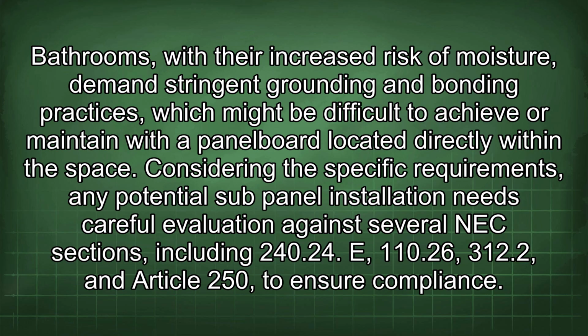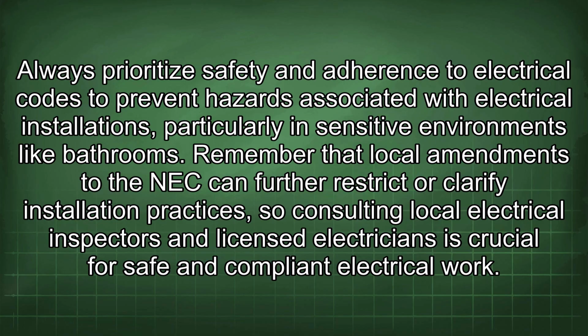Considering the specific requirements, any potential sub-panel installation needs careful evaluation against several NEC sections, including 240.24(E), 110.26, 312.2, and Article 250 to ensure compliance. Always prioritize safety and adherence to electrical codes to prevent hazards associated with electrical installations, particularly in sensitive environments like bathrooms. Remember that local amendments to the NEC can further restrict or clarify installation practices, so consulting local electrical inspectors and licensed electricians is crucial for safe and compliant electrical work.